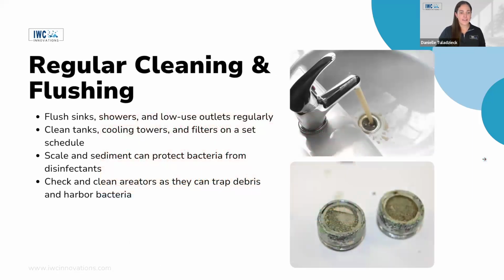Now that a system hopefully has hot water that's hot and cold water that's cold, we have to keep the water moving. Stagnant water is an open invitation for microbes, pathogens and non-pathogenic bacteria alike. When biofilms are given the opportunity to develop, they can provide layers of protection to Legionella, which the typical disinfectant levels supplied by your municipal water provider cannot combat. The Safe Drinking Water Act allows for the addition of oxidants up to only 4 ppm, which is not high enough to eradicate Legionella completely from the water. The low levels of bacteria entering the system will become a risk if allowed to proliferate through stagnation.